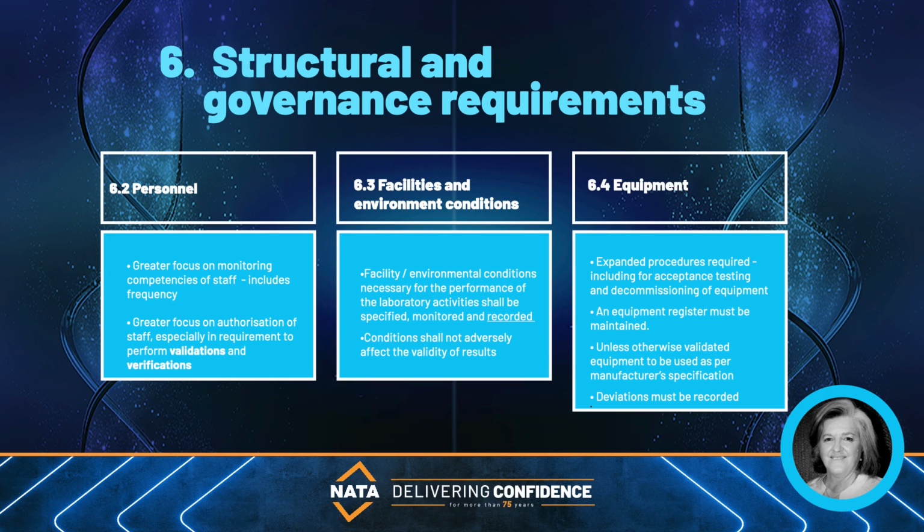Labs shall verify that the equipment conforms to specific acceptability criteria before being introduced or even returned to service. There is an emphasis on equipment used for measurement. It shall be capable of achieving the accuracy or uncertainty required to provide a valid result. Equipment shall still be safeguarded to prevent unintended adjustments, shall be operated by trained and competent staff, shall have instructions for use available, and shall be used as specified by the manufacturer unless validated by the lab.